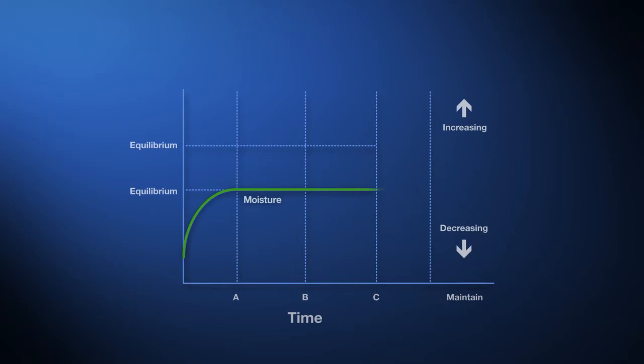Then over the majority of the lifetime of the oil, that moisture stays relatively stable, but as the oil starts to degrade, we'll start to measure an increase in that moisture content.